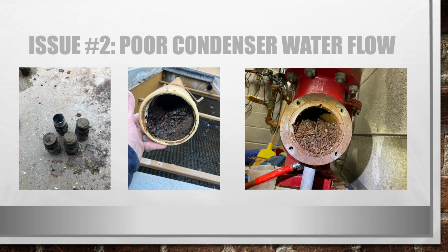Issue number 2, poor condenser water flow. This can be a result of dirty screens on the condenser piping. If you can see on the right there, that's supposed to be a screen for a suction diffuser on a pump, and it is completely full of rust chips. This can be caused by a bunch of different things.